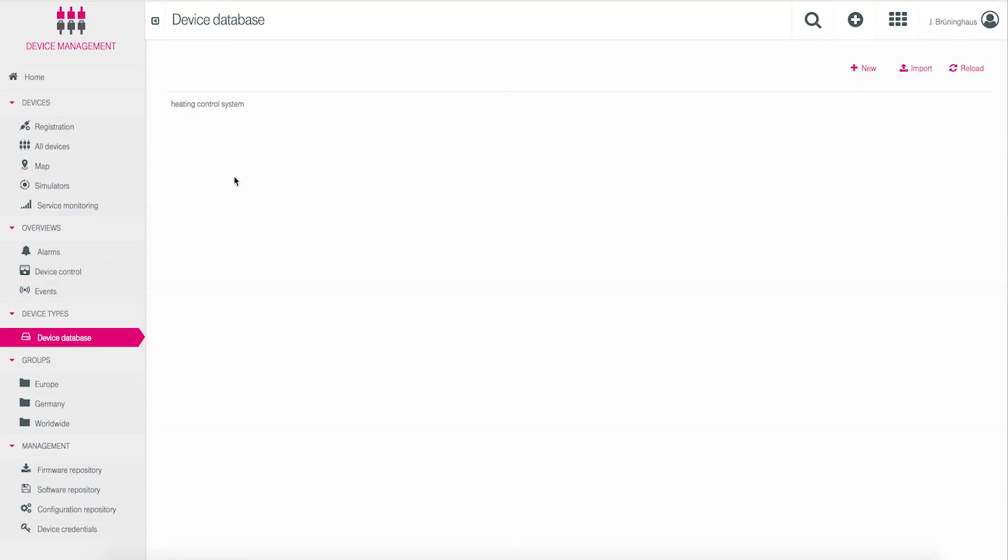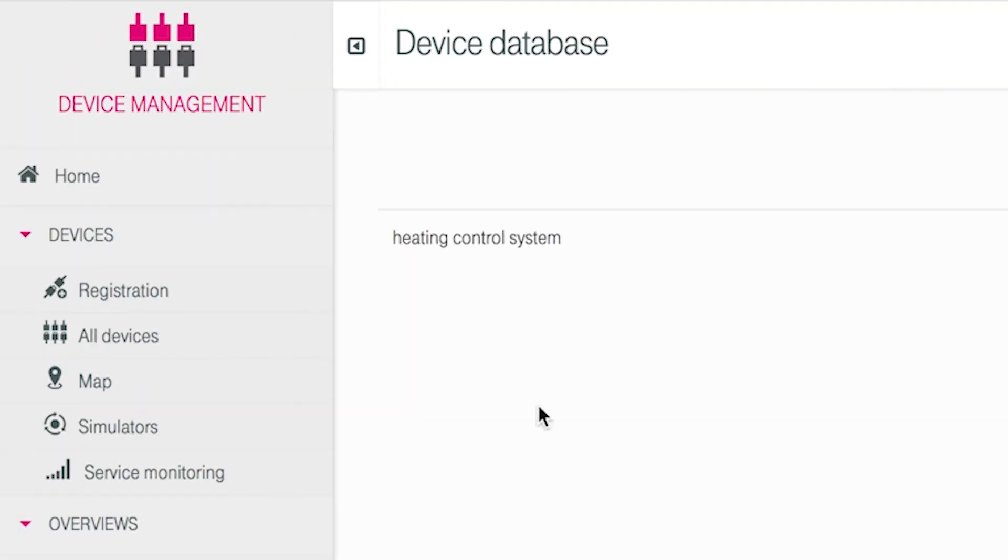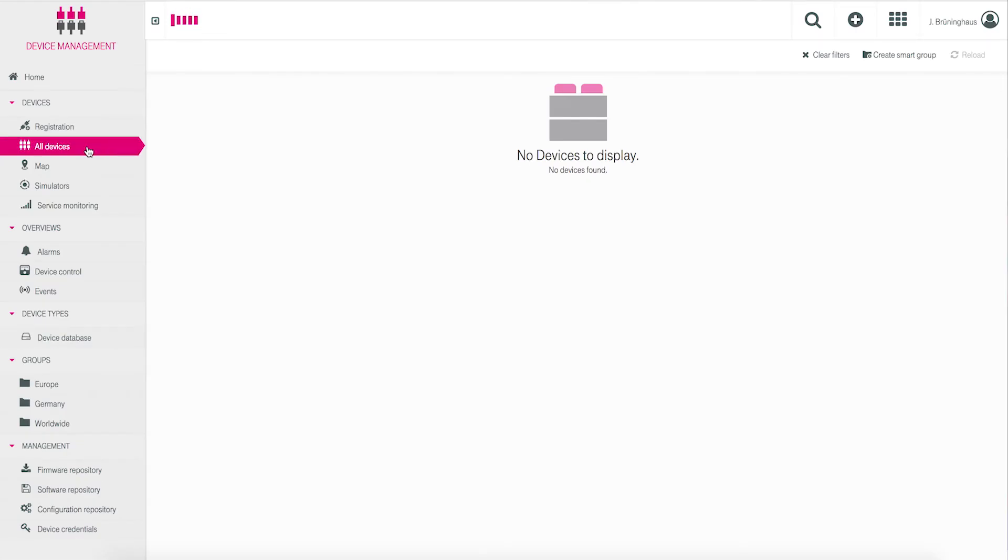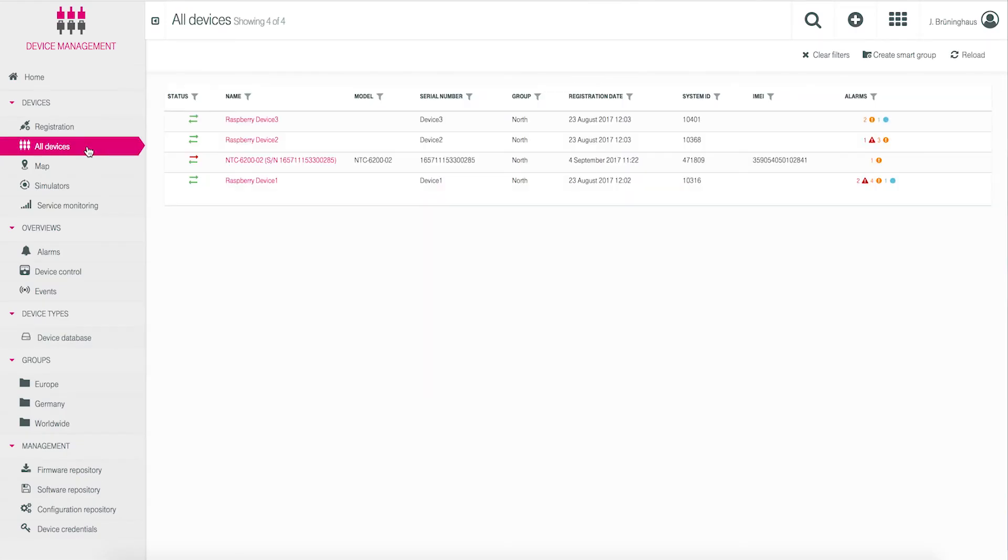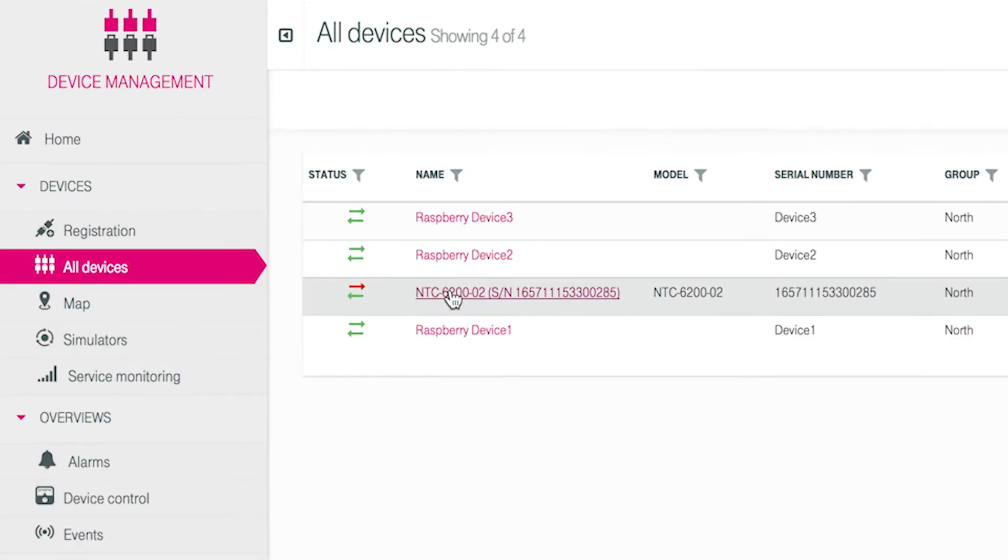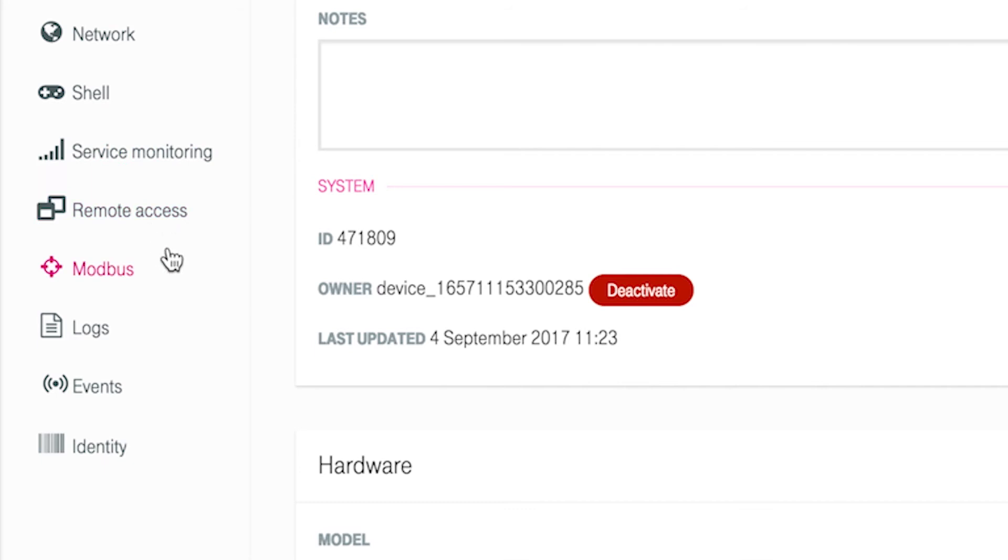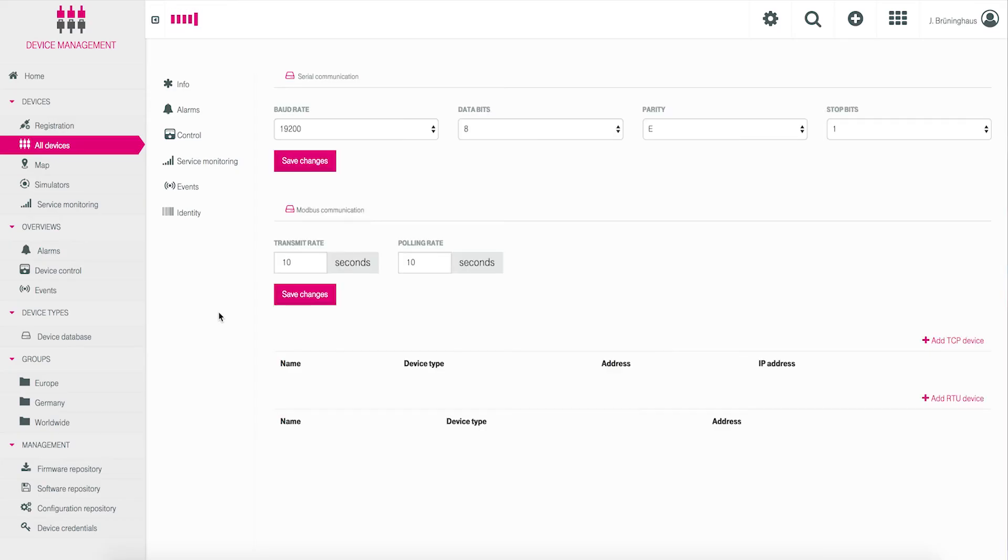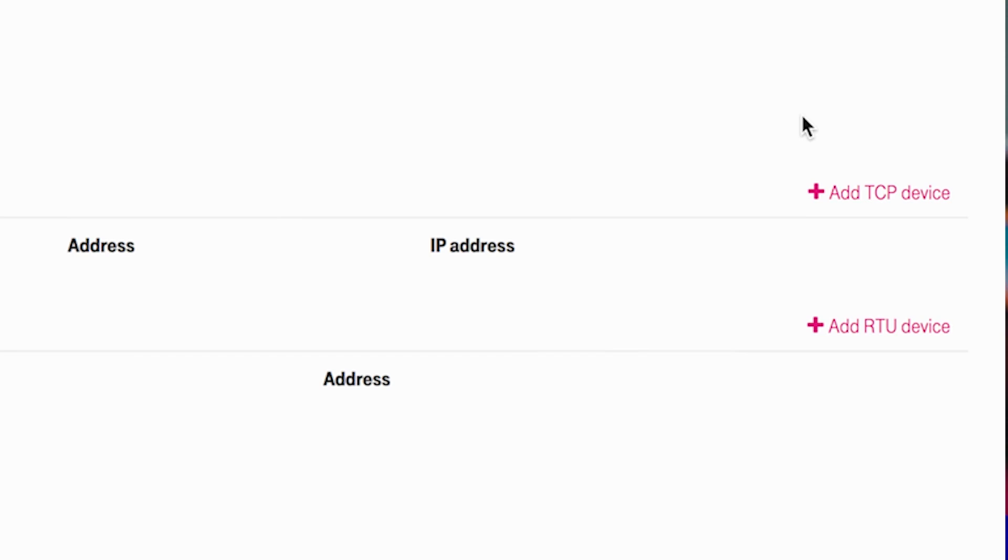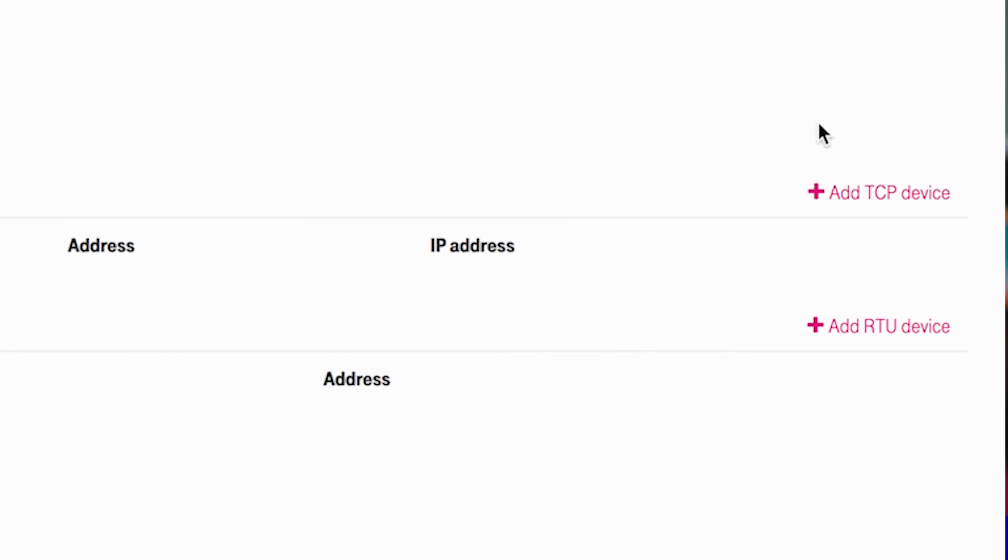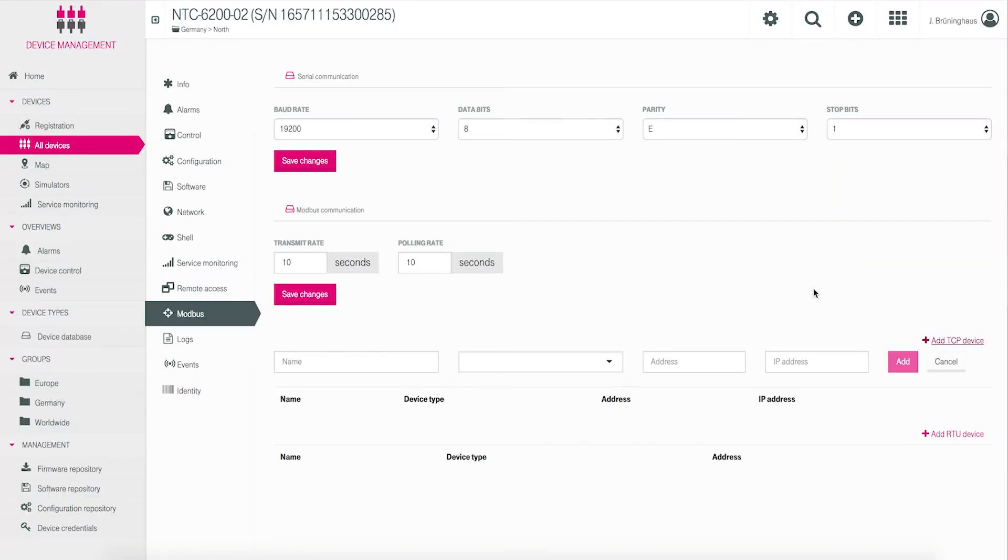The last step is creating a Modbus device as a child to our gateway. In device management, click on devices and all devices and select your NTC 6200 gateway by clicking the name. On the left side of the mask, you click Modbus and the Modbus definition mask will be shown. Click add TCP device because we want to establish this device as a child.